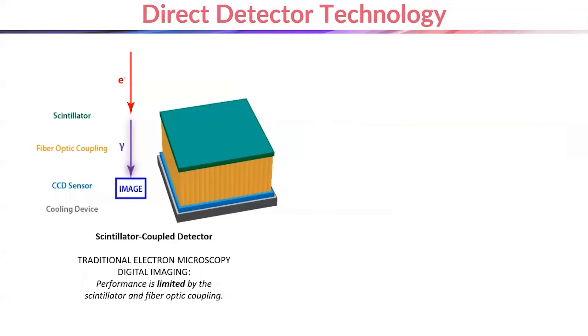Traditional detectors for electron microscopy use scintillators to convert electrons from the primary beam into photons, which are then transferred through a coupling to a sensor to form an image. The conversion of these electrons to photons and then the transportation of the photons through a coupling leads to inefficiencies and loss of signal and information.